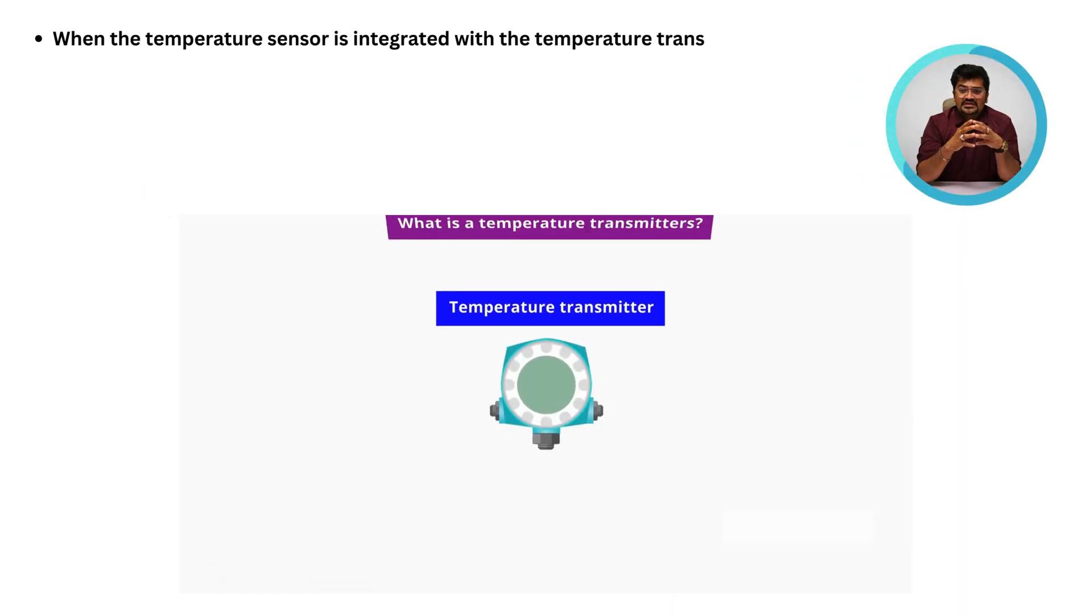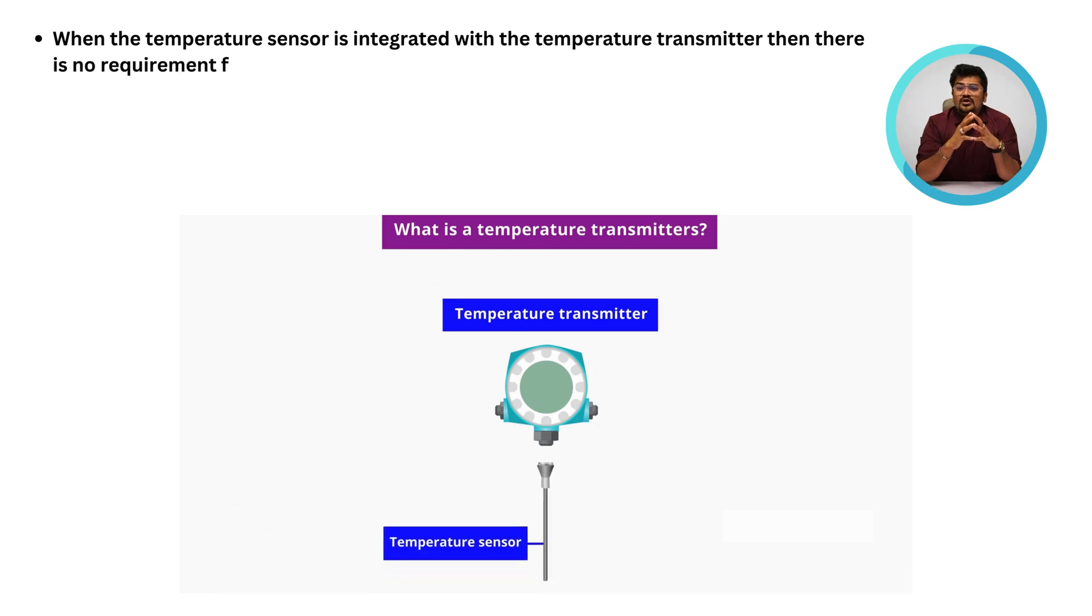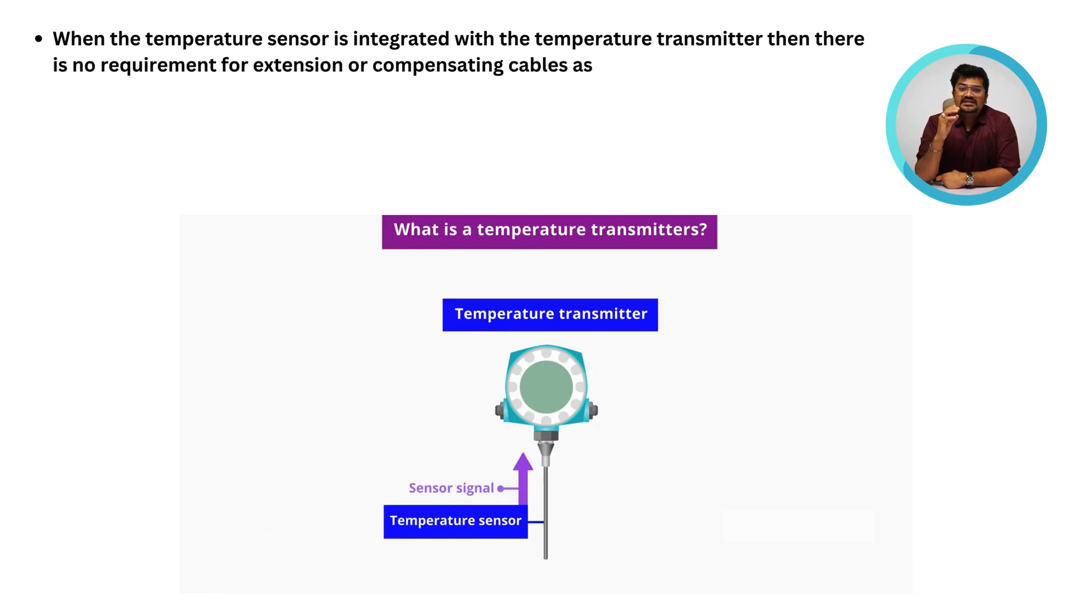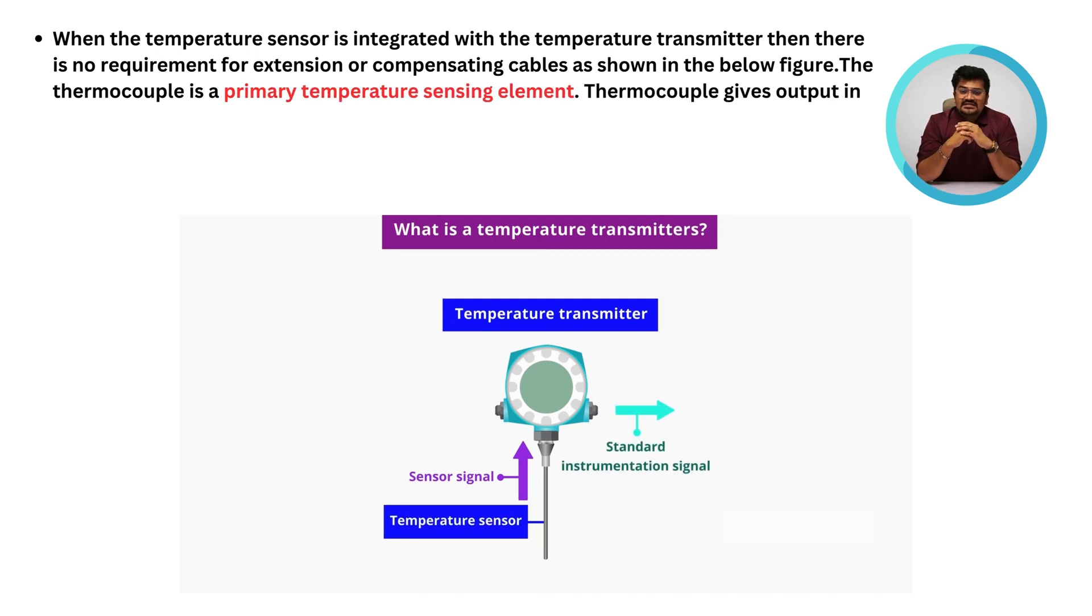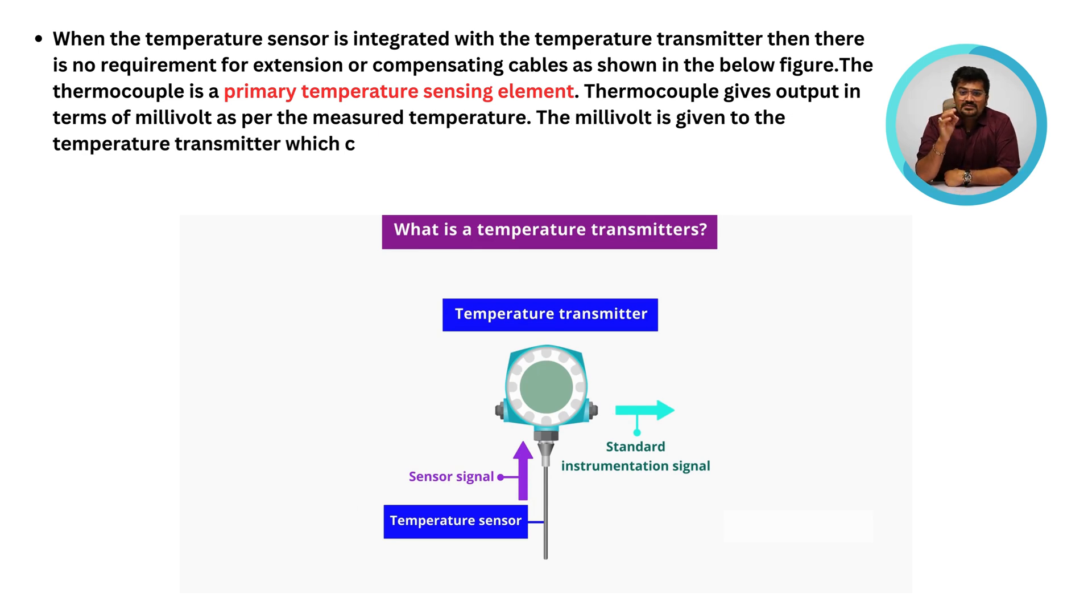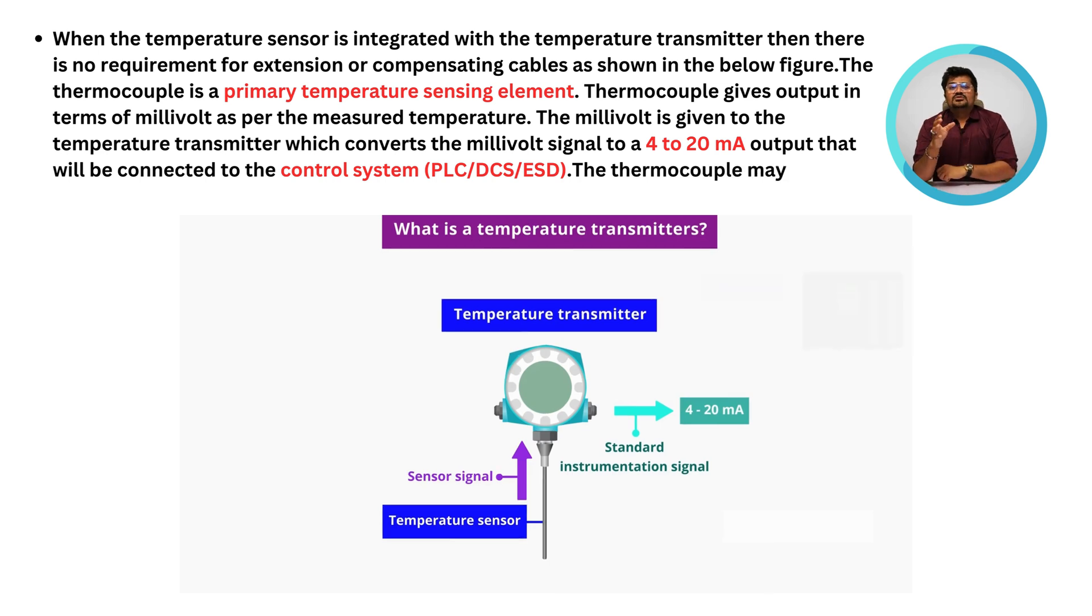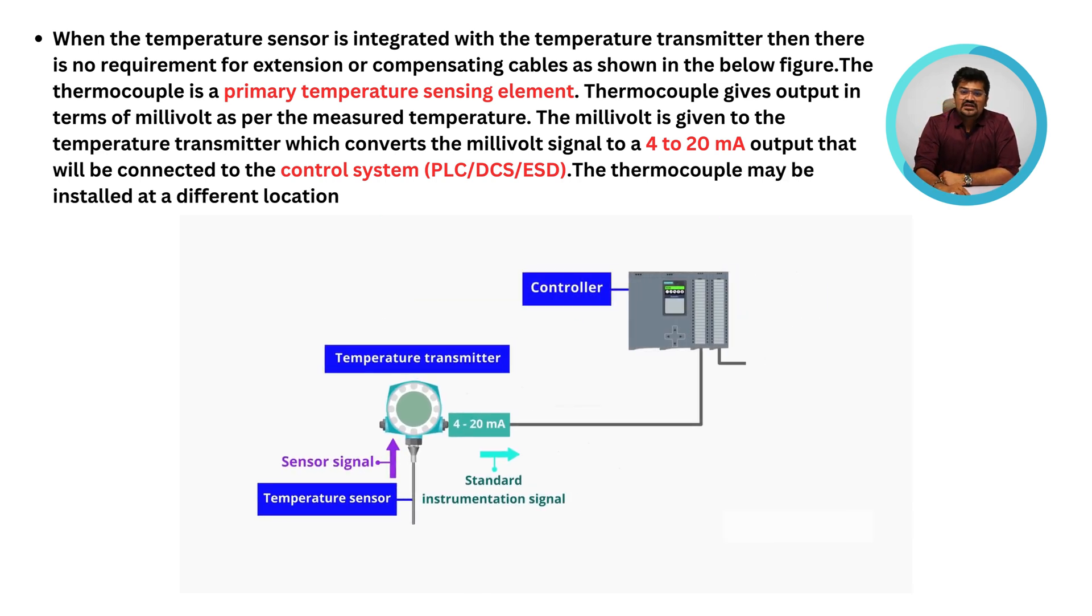When the temperature sensor is integrated with the temperature transmitter, then there is no need for extension or compensating cables. We can see this in the figure. The thermocouple is the primary temperature sensing element. The thermocouple gives output in terms of millivolts as per the measured temperature. The millivolt is given to the temperature transmitter which converts the millivolt signal to a 4 to 20 mA output that will be connected to the control systems like PLC or SCADA.